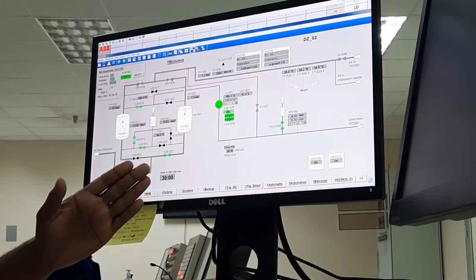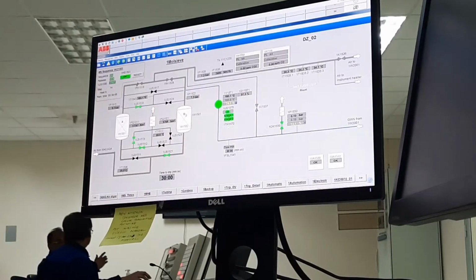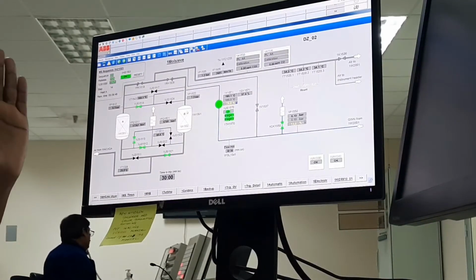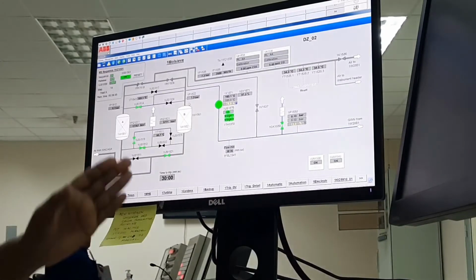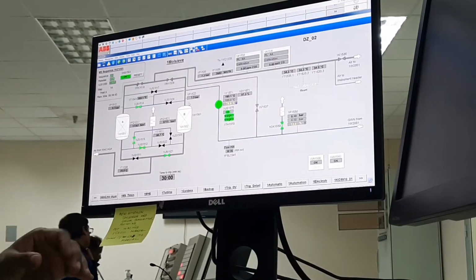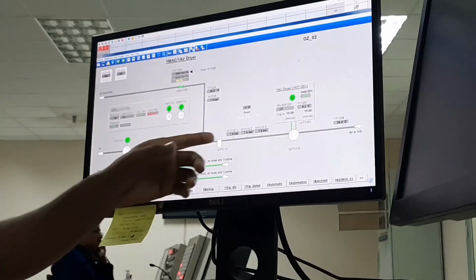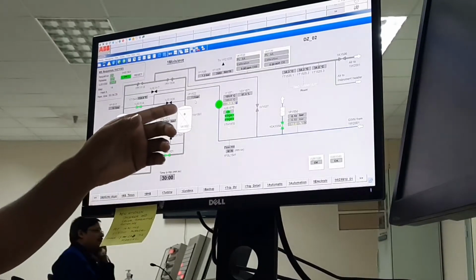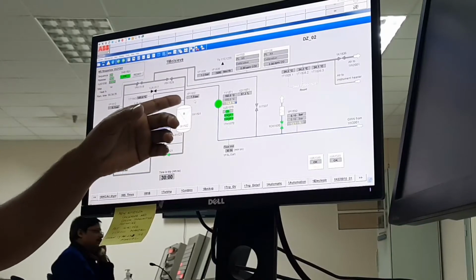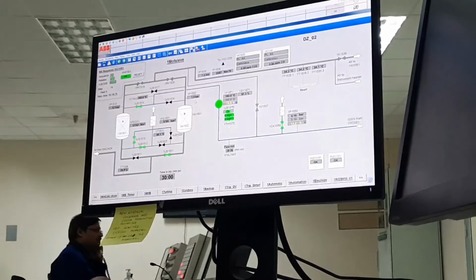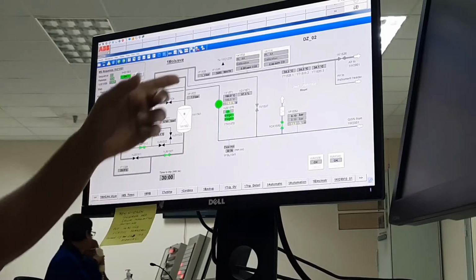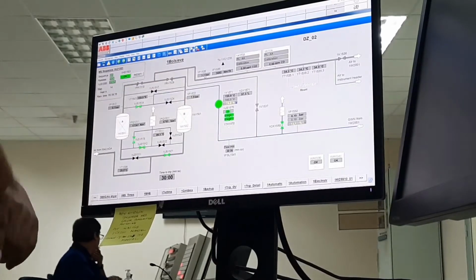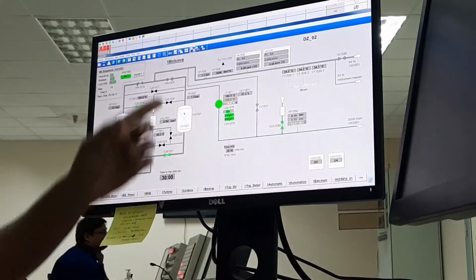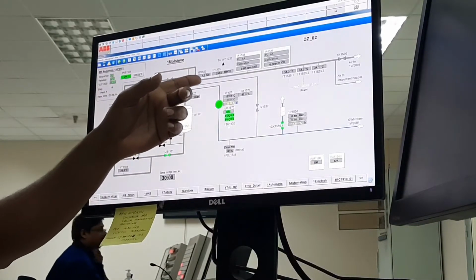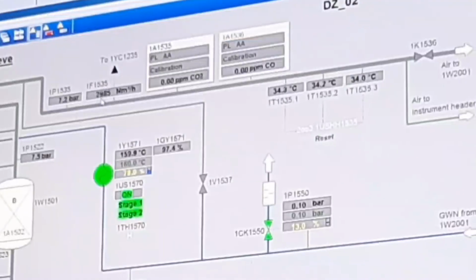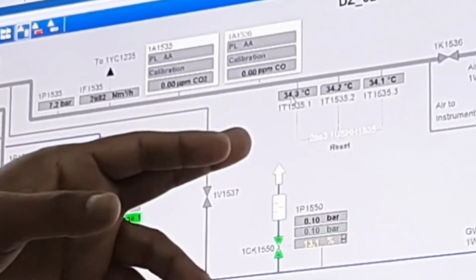30 degree temperature, 7.5 kg pressure, and 3000 flow, still 3000 flow. This 3000 flow will pass through this absorber. When it passes through the absorber, some pressure will reduce, because you see this side pressure is 7.6 kg. So after passing the absorber, pressure is slightly reduced to 7.5 kg. After passing this line, this side pressure should also be reduced, because this is a long line. So now 7.2 kg pressure, around 3000 normal meter cube of air, and 30 to 34 degree temperature.